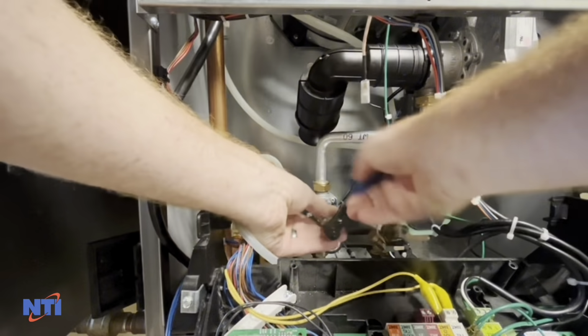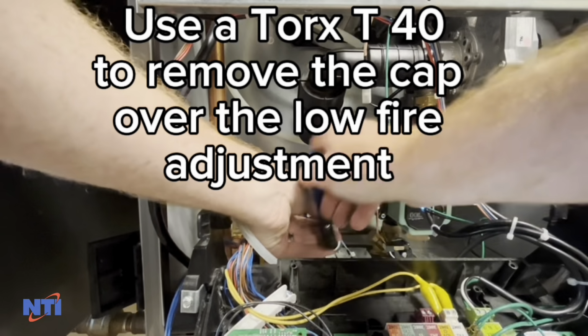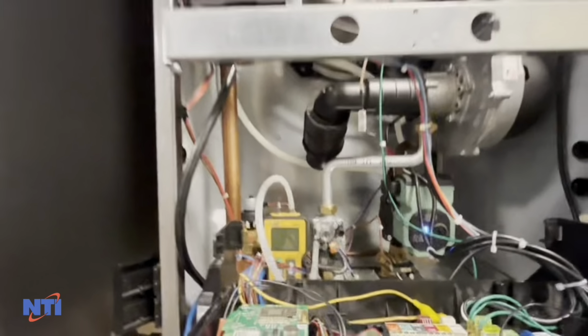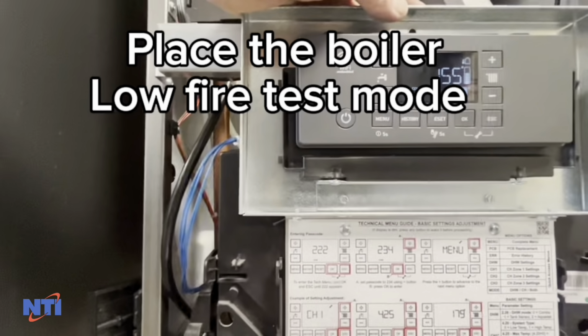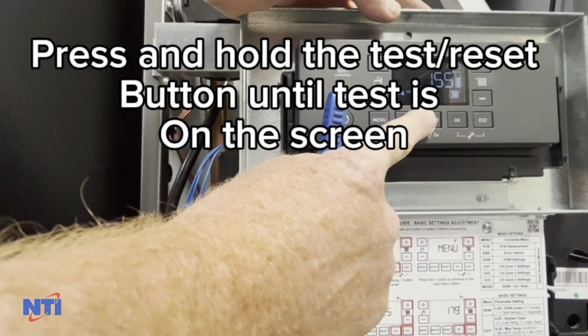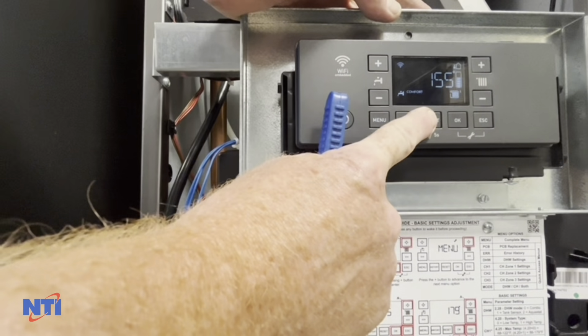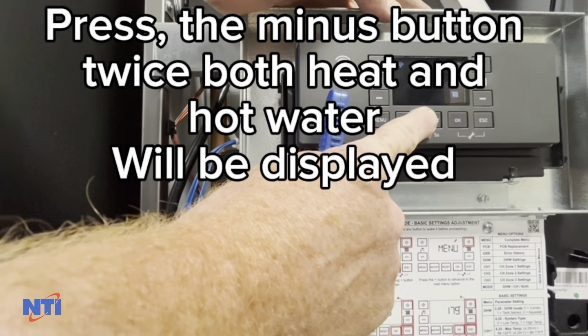Remove the cap covering the low fire adjustment screw using a Torx T40 screwdriver. Run the boiler in its minimum power test mode. Press and hold the test button. Once test mode is activated, hit the minus button twice so that you see both the central heating and domestic hot water icon on the screen.